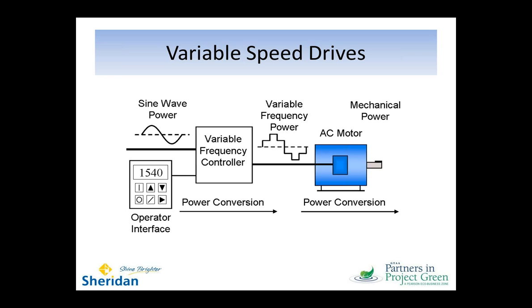These are, in my opinion, basically synonymous. I mean, variable speed drive, variable frequency drive, adjustable speed drive, all names for effectively the same thing. The one possible exception I may state here is that you can control speed at the process shaft both by adjusting motor speed, as in a variable frequency drive, but you can also do it by changing the coupling, like we saw with the magnetic drive. So you can adjust speed in a couple of different ways.